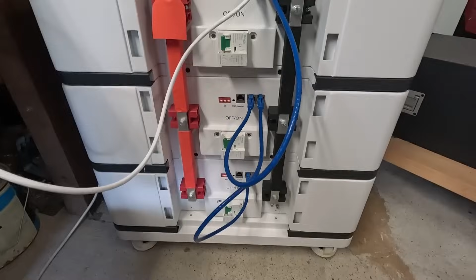Now the BMSs are talking to each other and they figure out the communication addresses automatically. But as I said at the beginning, the downside is if you want to change the settings on one of the BMSs, you need to unplug this communication, because you need to get your communication cable into port number 1. And you also need to terminate the communication to the other battery.